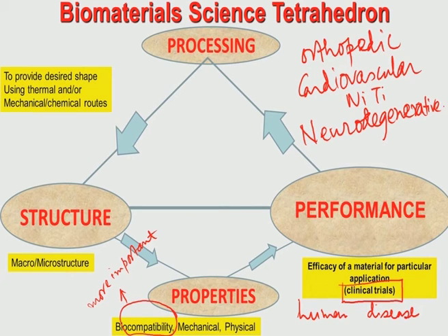Any time the device design concept is changed, or at any given point the material composition is changed to any significant extent, the material has to be tested all the way from physical property measurements to biocompatibility assessment, both in vitro and in vivo or preclinical study, and then subsequently clinical trials, before the material can be considered biologically safe to be used in biomedical applications.